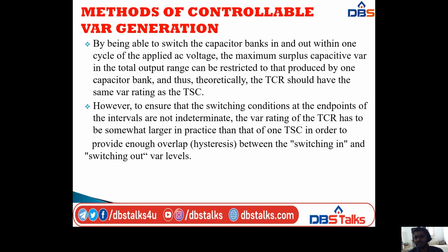However, to ensure that the switching conditions at the endpoints of the intervals are not indeterminate, the VAR rating of the TCR has to be somewhat larger in practice than that of the one TSC, in order to provide enough overlap between the switching in and switching out VAR levels.